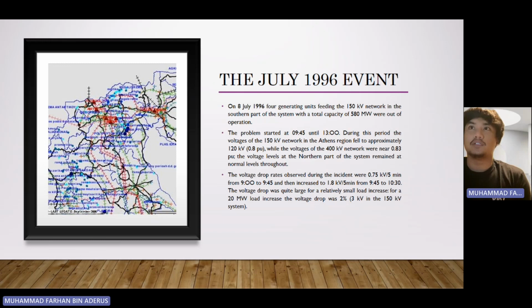On 8 July 1996, four generating units feeding the 150 kV network in the southern part of the system, with a total capacity of 580 megawatt, were out of operation. The problem started at 9:45 am until 1 pm. During this period, the voltage of the 150 kV network in the Athens region fell to approximately 120 kilovolt, which is 0.8 per unit, while the voltage of the 400 kV network was near 0.83 per unit.